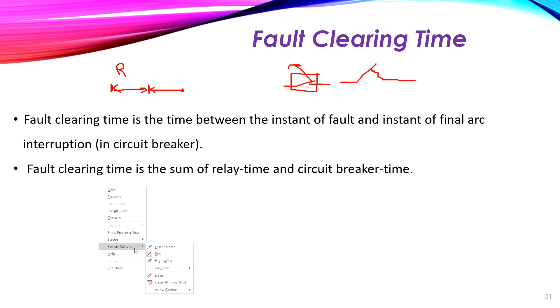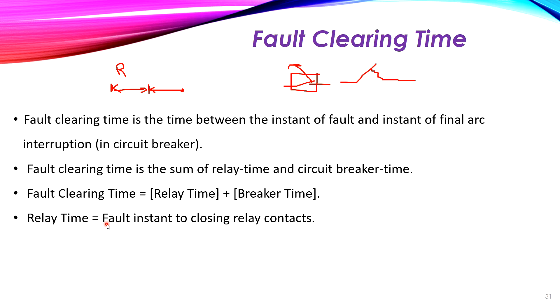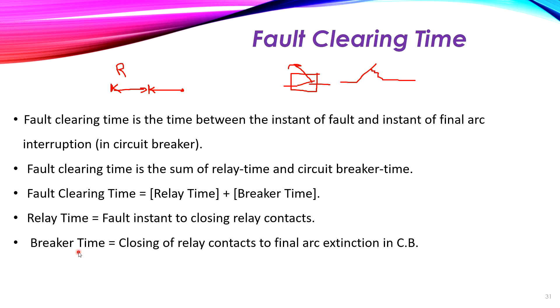The fault clearing time is the sum of the relay time plus the circuit breaker time. The relay time is the duration from the fault occurrence instant to the closing of the relay contacts. The breaker time is from the closing of the relay contacts to the final arc extinction inside the circuit breaker.